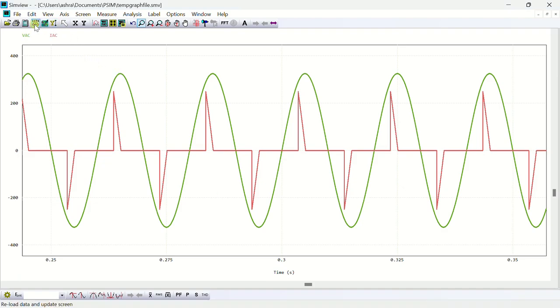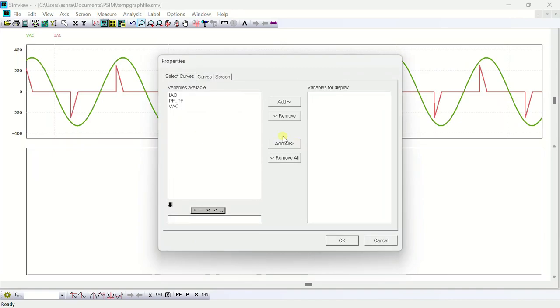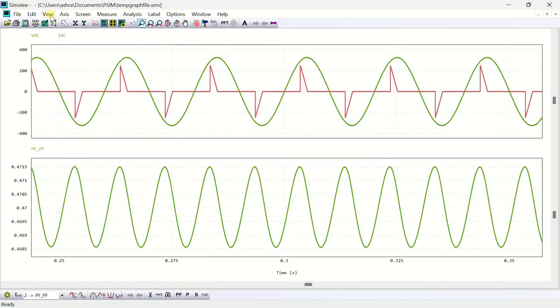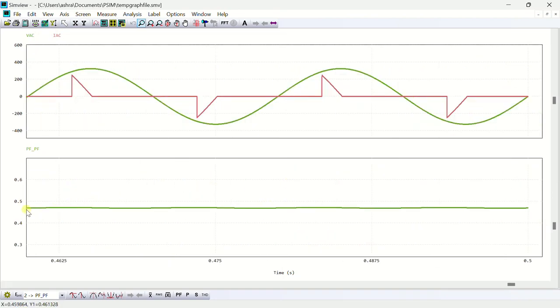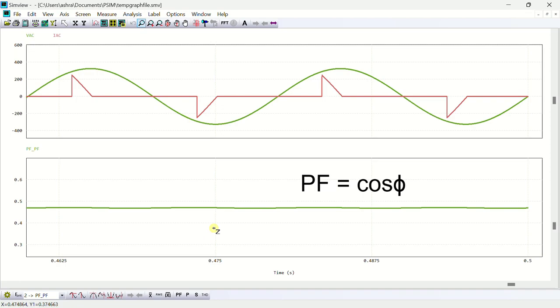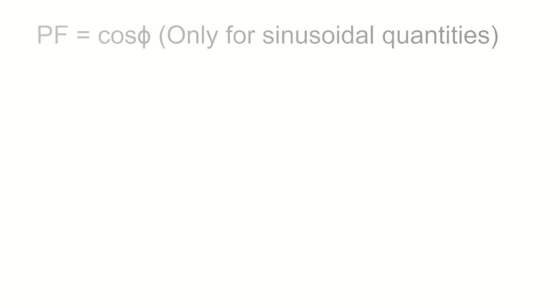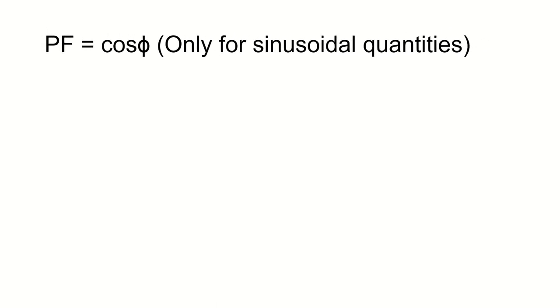Now we look into the power factor. Even though here both the voltage and current are aligned in phase, we are getting a power factor of only around 0.5 and this value is very low for a power supply. Normally for the calculation of power factor, we take the cosine of the angle between voltage and current. And this method is only applicable when both the voltage and current are sinusoidal quantities. Here since both the voltage and current are aligned in phase, some people wrongly assume that the power factor is unity.